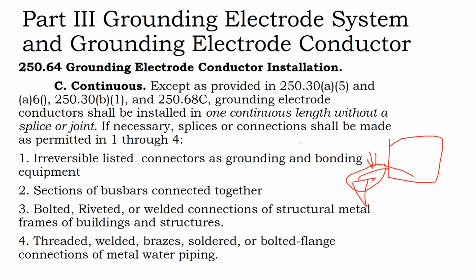So that needs to be continuous. And you can take bare copper crimp tools to permanently crimp the copper together. I can tell you that it's nowhere near as good as designing your building so that you don't need to do those permanent crimps. But you might be wanting to ground your whole solar array together. And so you're saying, well, does that mean if I have bare copper wire up to the array, do I have to run that bare copper throughout the entire array without splicing or crimping it?